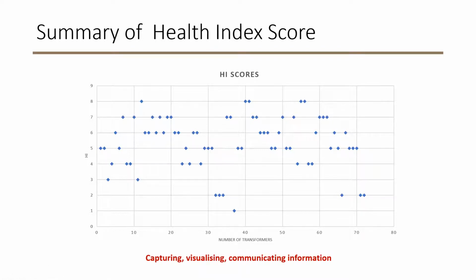So the lifespan of the transformer is reduced by 15 to 20%. Remember, these are working transformers with no fault, nothing has happened to them. It's just an assessment of where to invest OPEX and some CAPEX to manage and extend the life of the transformer. So this is the distribution of the HI score, and from here your upper management can see what actions are needed.